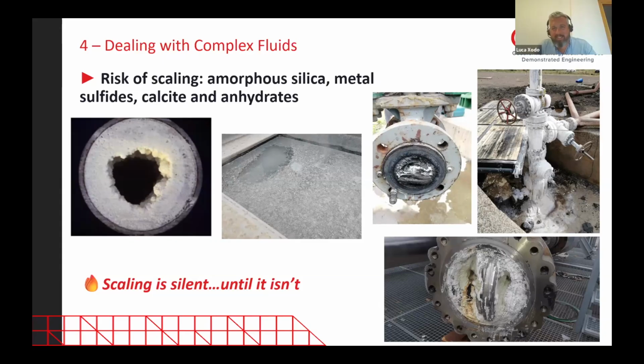The other pictures show problems with valves, during commissioning and operation. The bottom one was calcite - it was a valve that wouldn't close, so we decided to stop production. We opened the valve and found that it was completely stuck because of calcite deposits. Whatever we were dosing at that moment wasn't enough to avoid the scaling and precipitation of calcite.